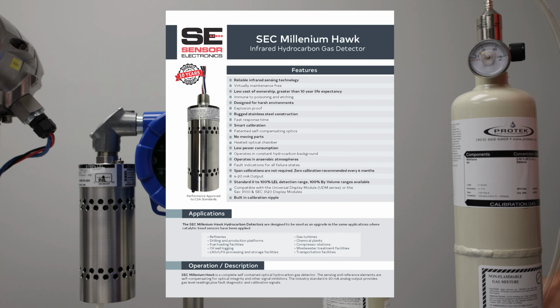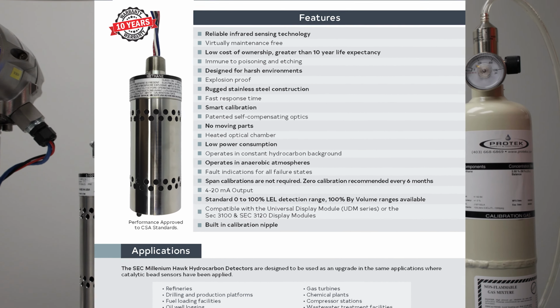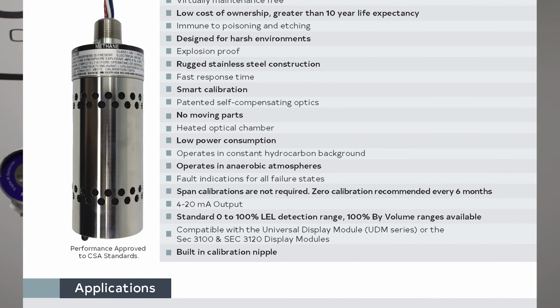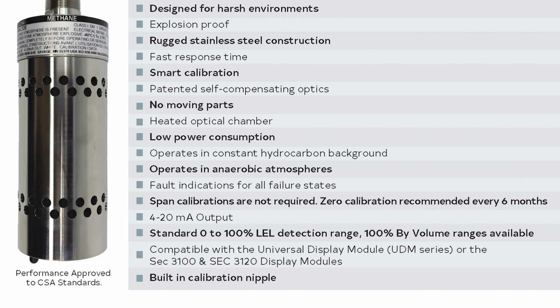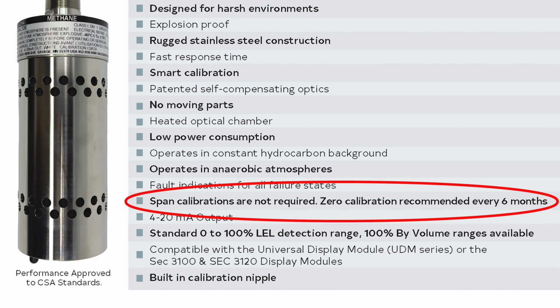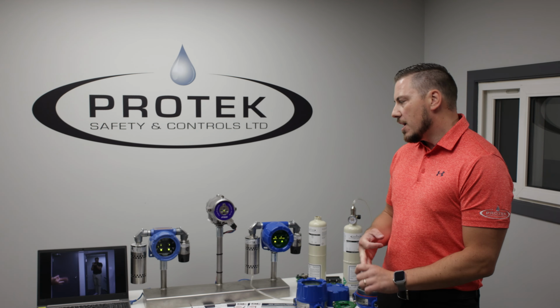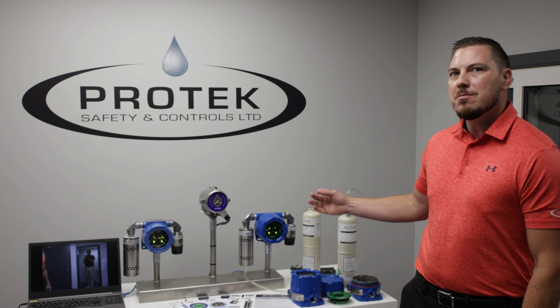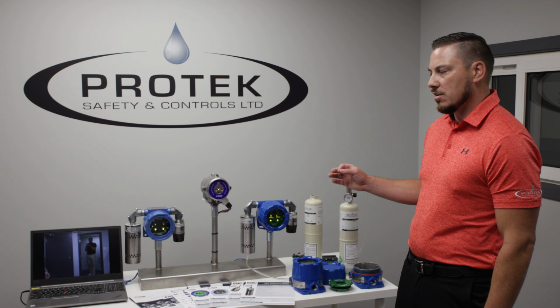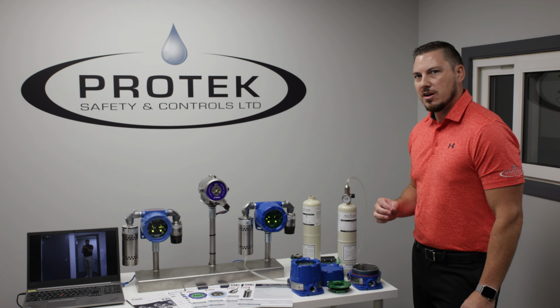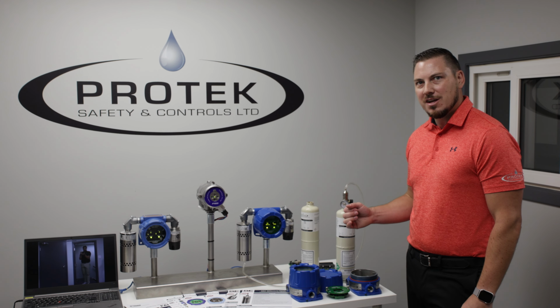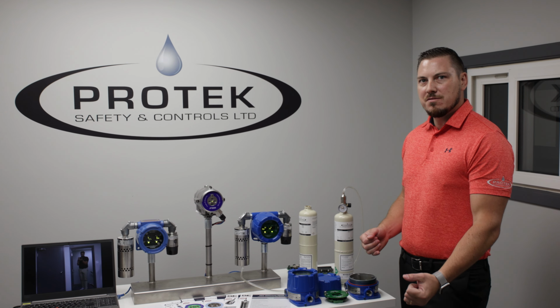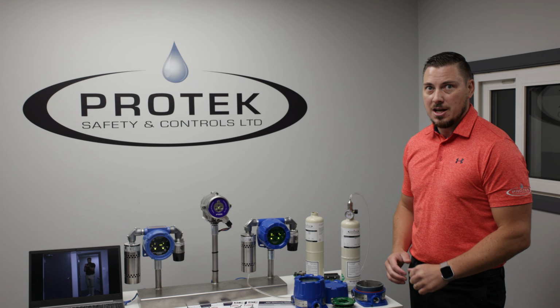Now one thing I'd like to touch on is sensor electronics. If you take a close look in their manual, they don't actually require a calibration. So they require a 0 cal upon installation, 6 months, and every year. So the span actually is not required, but it can be done in the field, which is something that's very specific to sensor electronics and the technology. It being solid state, it can be factory calibrated, sent to the field, and it doesn't require a calibration again.